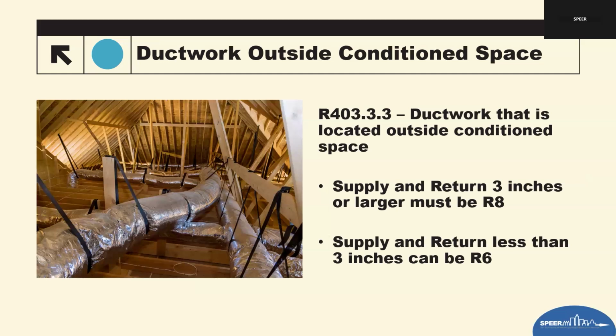Anything less than 3 inches can be an R6. For small branches, we've not really ever seen anything less than 3 inches. Those are typically short jump ducts or small supplies for closets. Usually we see a 4-inch in there, and that's still going to require R8. Especially in hot climates like Texas, where temperatures routinely exceed 120 to 140 in an attic, this is where we lose a tremendous amount of cooling energy to conductive heat inside the attic. So we need that at an R8. For field installation requirements, inspectors should check the labeling on the duct insulation.